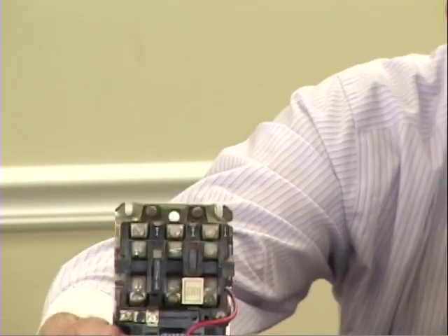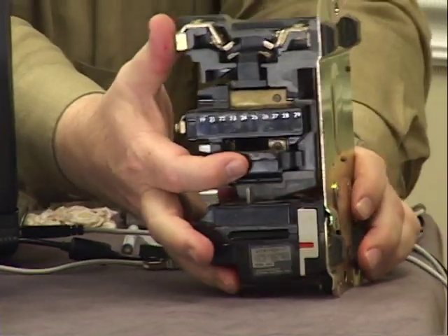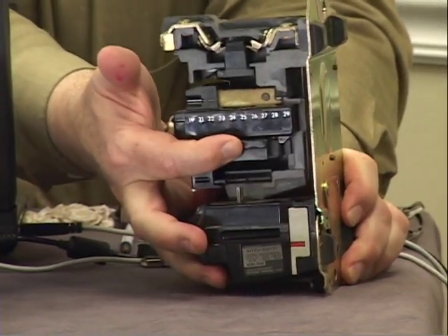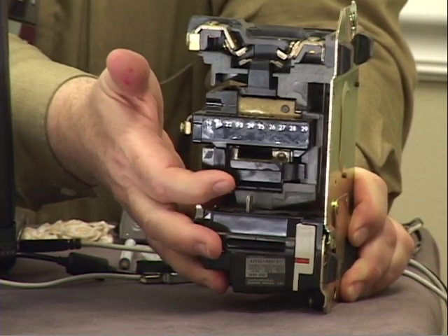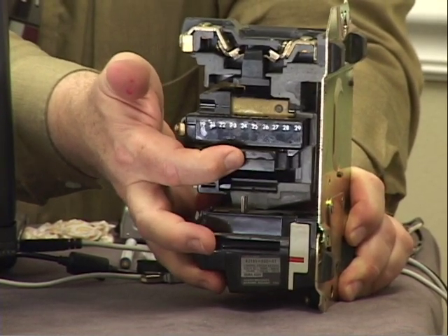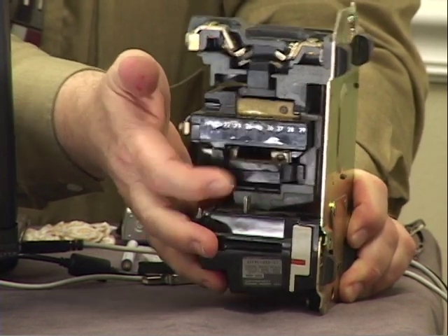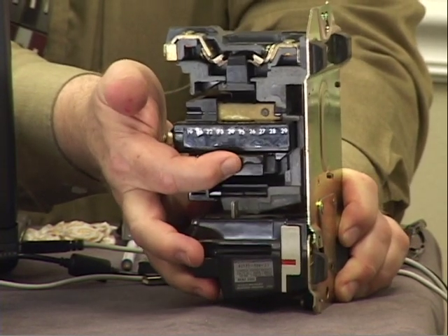Steve, do you have something you can show us, a cutout, so we could get a real good zoom on this? Get my finger in the right place here so I can show you. This raises up when it's energized, and then it depends on gravity when you de-energize it to drop back down. If you can see that cutout there, there's no spring there. It's just using gravity to drop it out. Right, this is just using gravity.